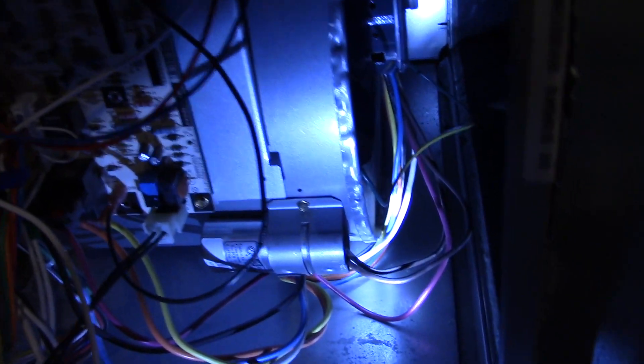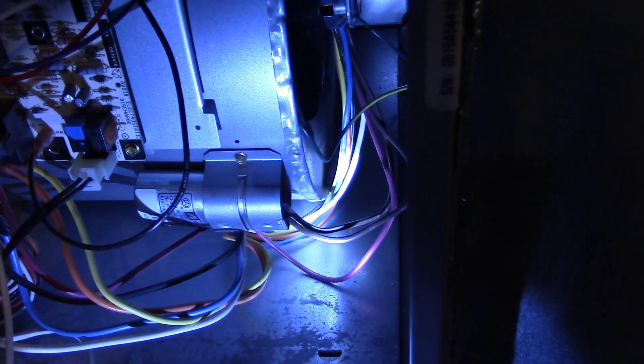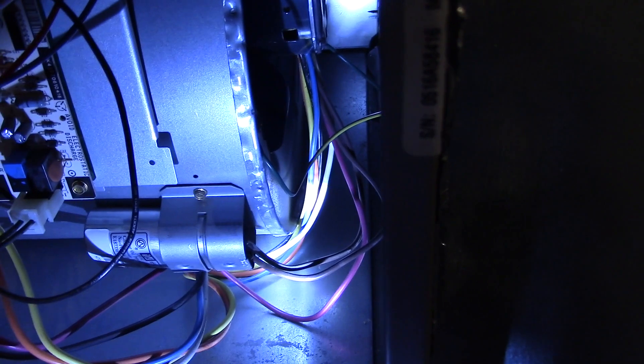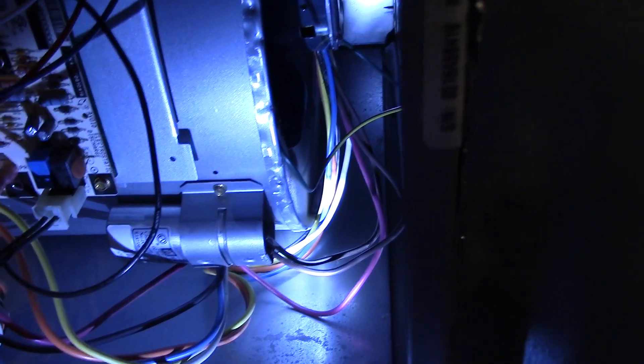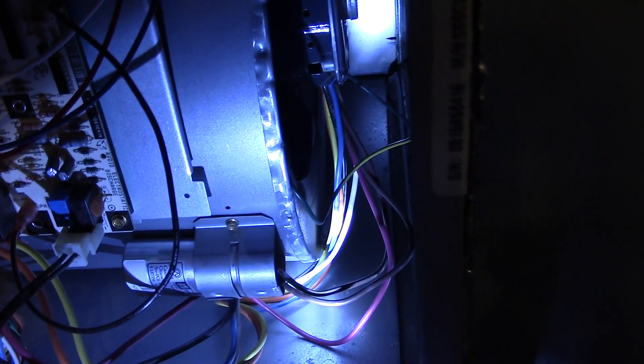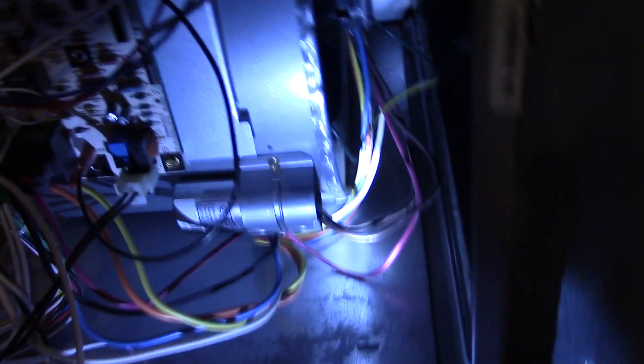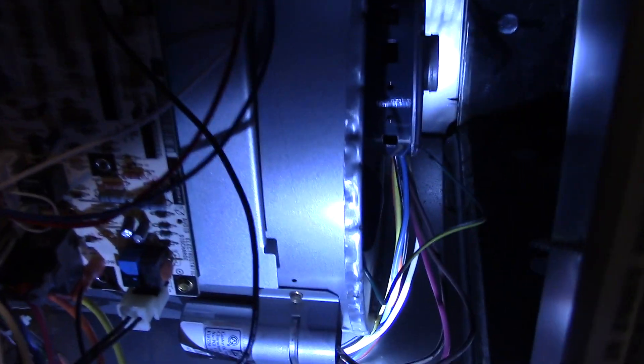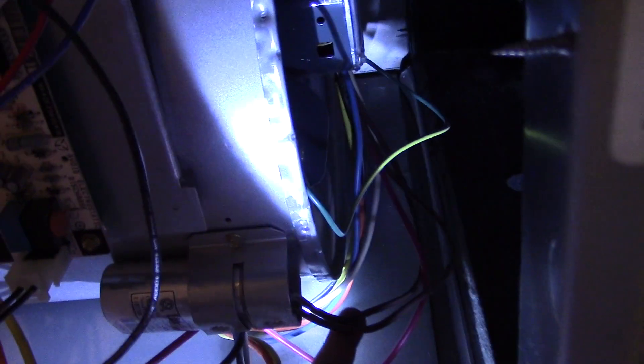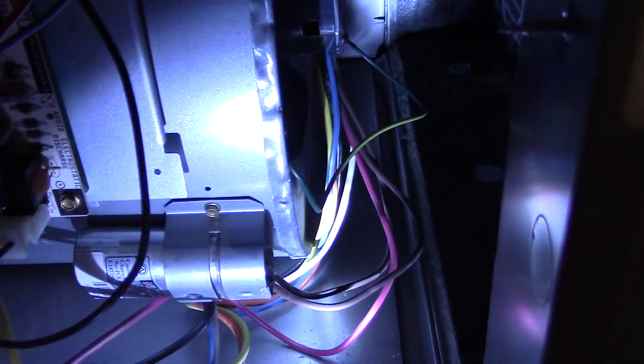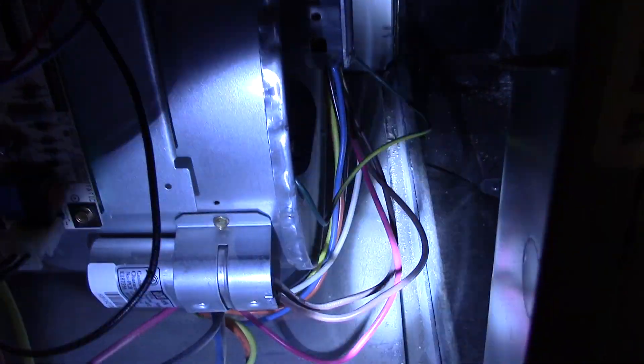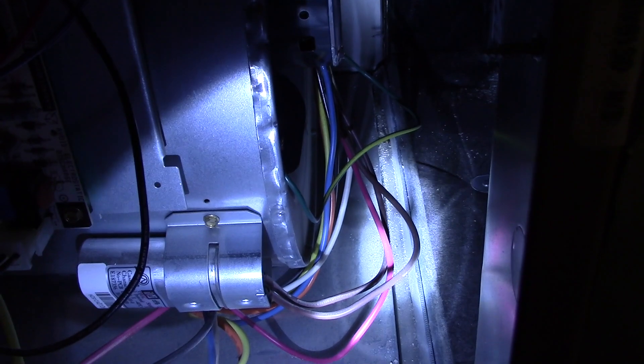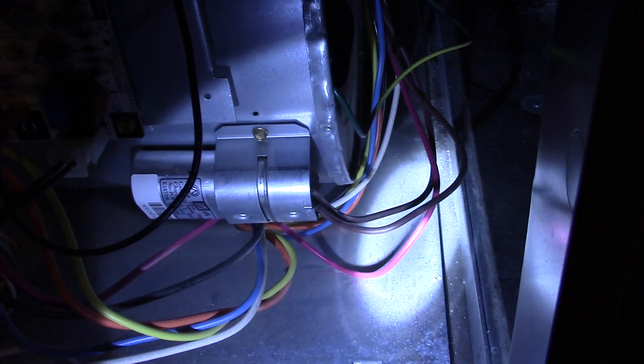Now on most furnaces you'll have this motor, which is called a PSC motor, which means permanent split capacitor. And here's the capacitor right here for it. Basically the number of speeds you have will be the number of wires you have. This particular blower motor is five speed. The first thing to note is we have two brown wires here. Those go to the capacitor.